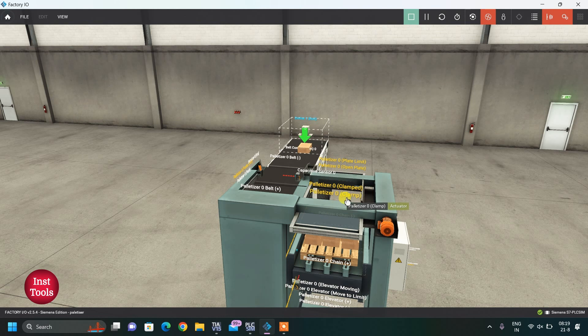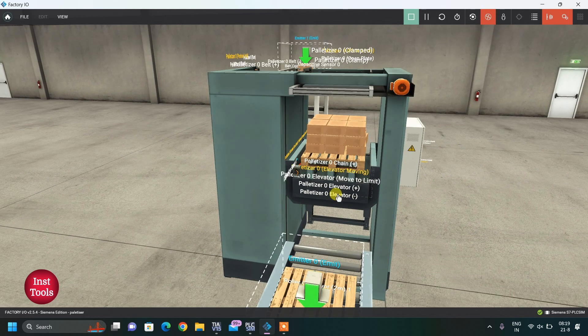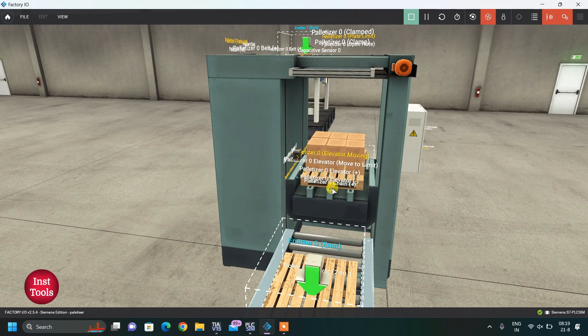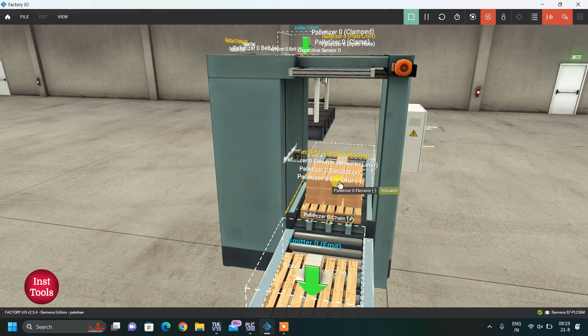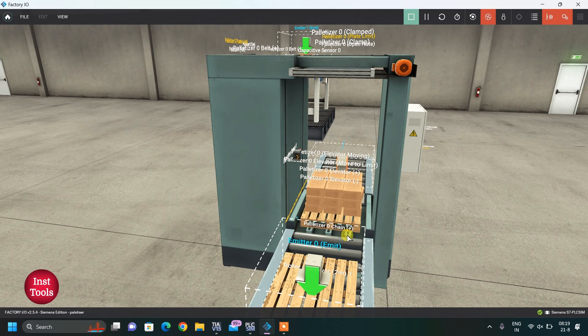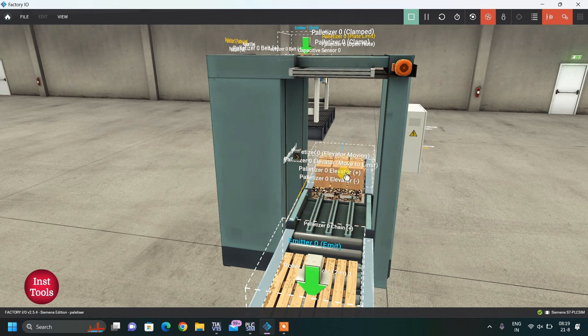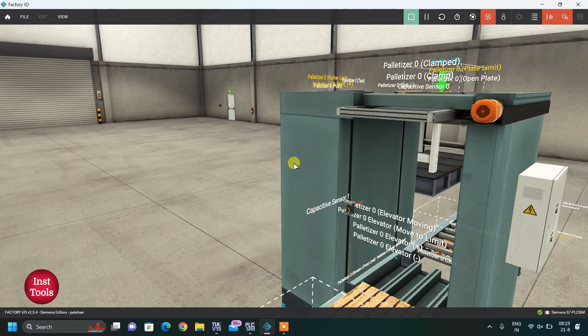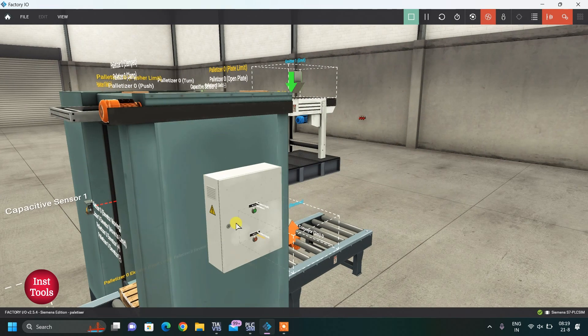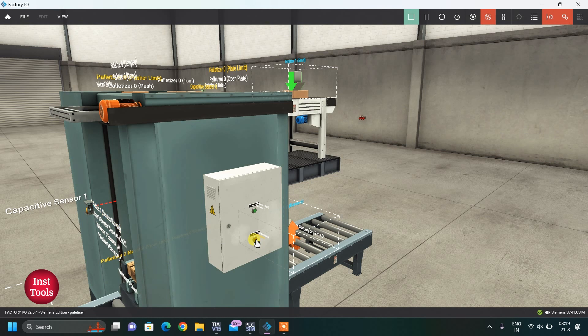Now it will unclamp and the door will close, then the elevator will come down. You can see the elevator coming down, and then we start the chain conveyor and roller conveyor again so boxes are unloaded and a new pallet will come. I can stop this process anytime by pressing the stop button, and all outputs, counters, and timers will be reset.